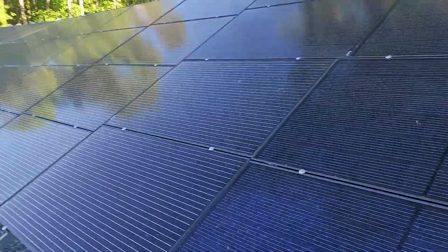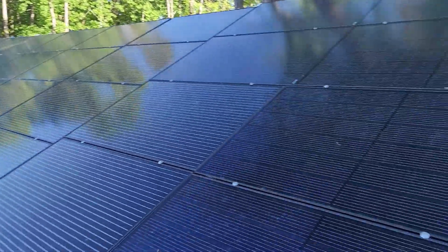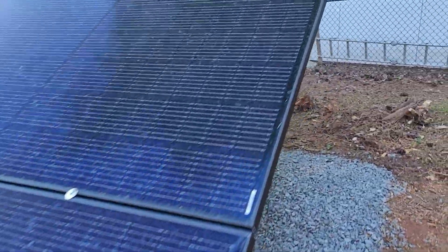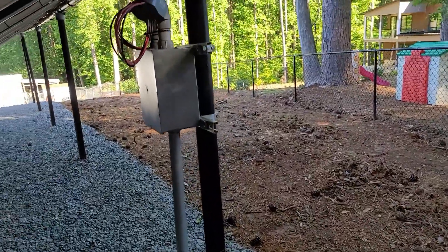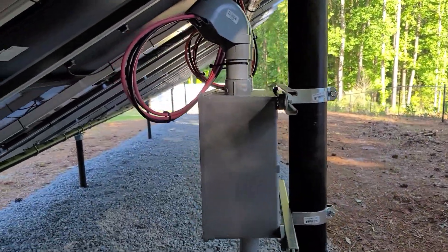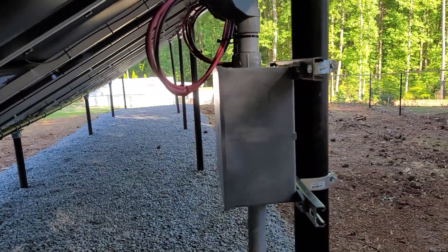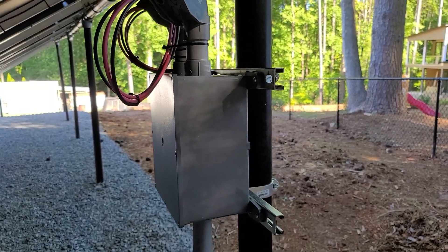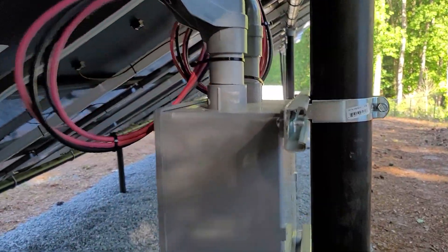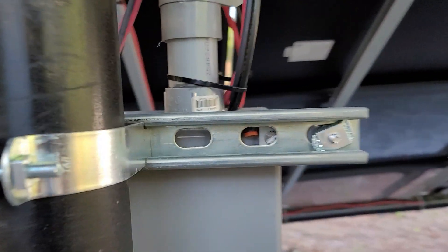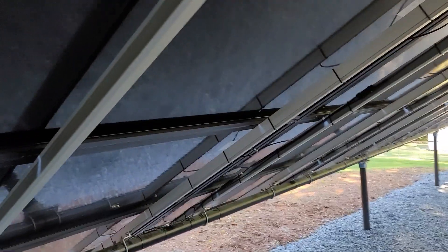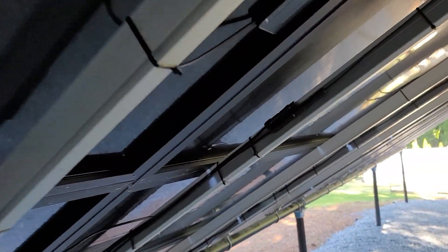There's some bird droppings and whatnot but they normally get washed off by the rain. We didn't have that much rain in the month of April. So far everything looks nice and tight on this side. Let's go take a look at the backside combiner box or the box where all the cables come in and they transition into the cable that needs to go underground, which would be a THWN-2 cable.